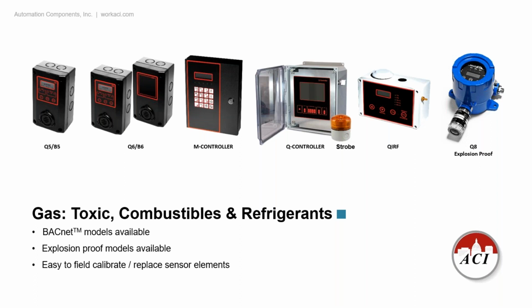The QIRF is actually our Freon or our refrigerant leak detector. The only one in the marketplace that you actually are able to select on board what Freon you want to sense. So say you have an R22 chiller, use an R22 Freon, you order that QIRF set up for an R22 from ACI. You get it and they changed out the chiller and now all of a sudden it's 134A. You take the pen that's magnetic that comes with the unit. You go into the front keypad, you select R134A, click enter, and you're sensing 134A now. No other Freon or refrigerant sensor in the marketplace offers that flexibility.